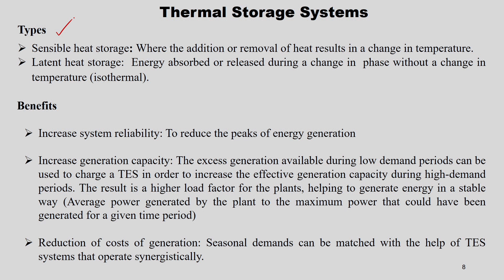In types of thermal energy storage, there are two categories: sensible heat storage and latent heat storage. In sensible heat storage, addition or removal of heat results in a change in temperature. In latent heat storage, energy is absorbed or released during a phase change without a change in temperature — it is an isothermal process. Benefits of thermal energy storage include increased system reliability, reduced generation peaks, and increased effective generation capacity during high demand periods.